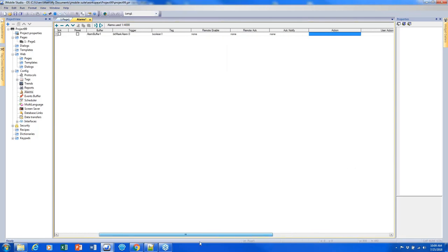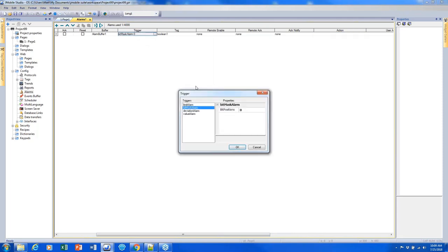We can do things like set a tag, show a dialog, load a page or change the page. You can also launch JavaScript or send an email — common for notifying an administrator or operator that an alarm has been thrown. Going back to alarm types under trigger: we had bit mask alarm. If the tag was not a boolean — say it was a short, which is 16 bits in J-Mobile — I could choose bit position 3 or 4, and if that bit became a one, the alarm would be thrown.